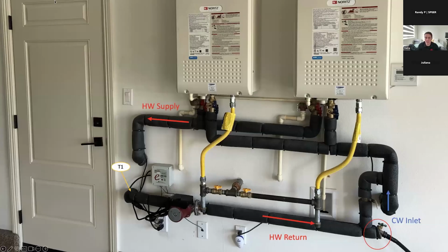So here is a picture of a hot water recirculation system where you have the tankless water heaters, your hot water supply going out to the house, and then your hot water return line coming back, which is completing the loop. Where it says T1 here, this is where the temperature sensor is located. And then you can see where that bleeder valve is located downstream of the pump. You want to make sure that the bleeder valve is downstream of the pump, because if it's upstream of the pump, then potentially you'll never be able to fully purge air out of where the pump is.